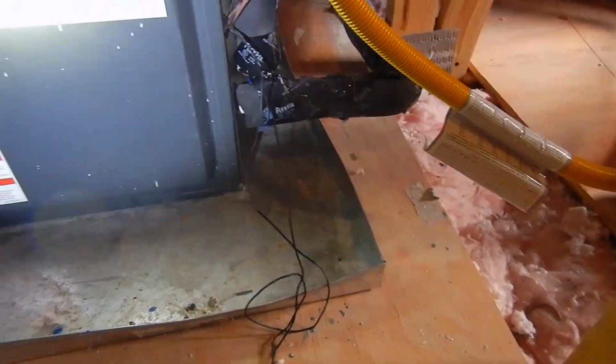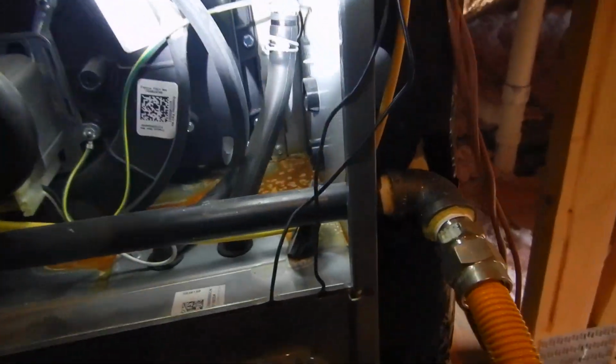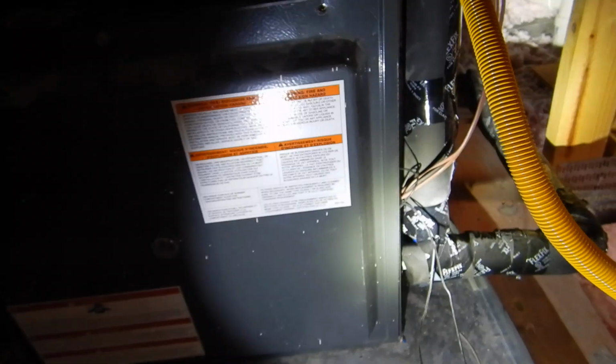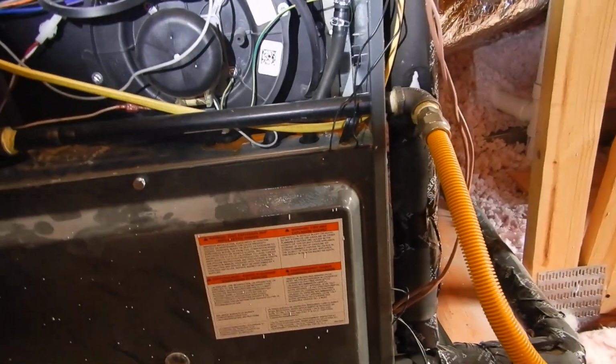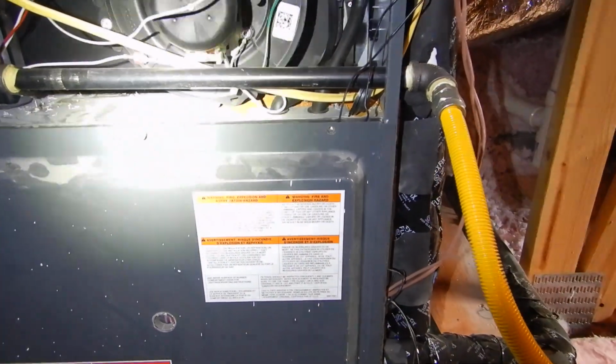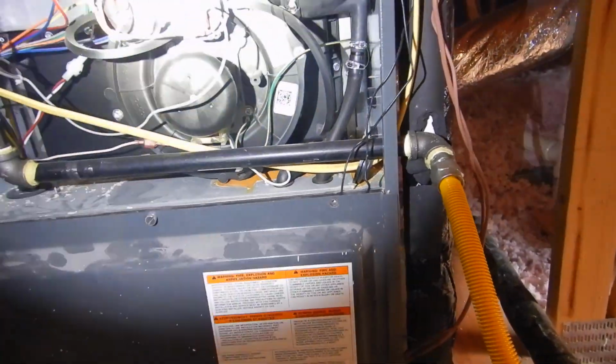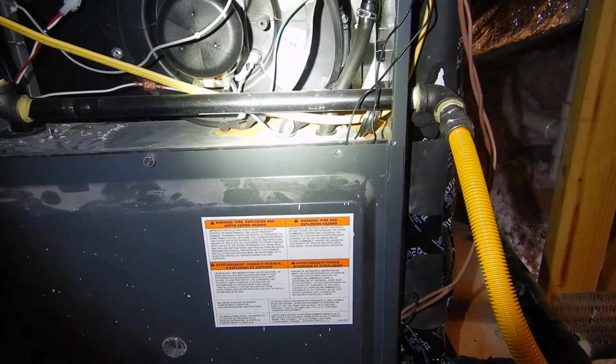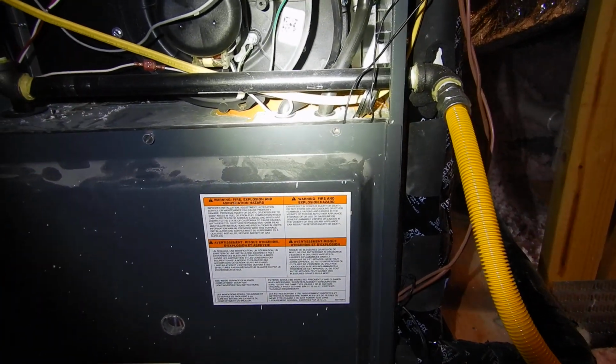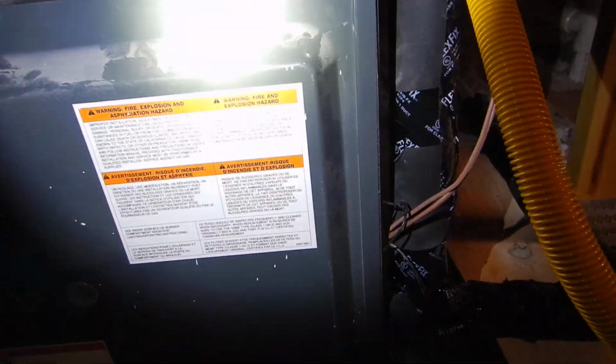Okay, now this furnace, we don't have our care and use manual, but this furnace is a high efficiency furnace. That's why we can have our plastic pipes. All right, now high efficiency means that it makes condensate. Oh, condensate like that right there? Yeah, condensate like that right there. Now, most of the heat is extracted. We use the heat that we created, and we enjoy the heat instead of just blowing it out the wall. But it's still exhaust. And because it is so energy efficient, it condensates. And so that condensate is acidic. All right? And this condensate drain line comes down here and goes into...